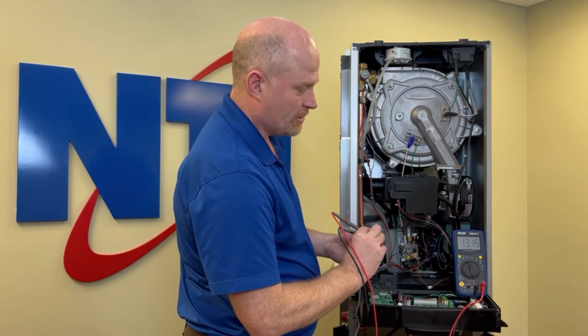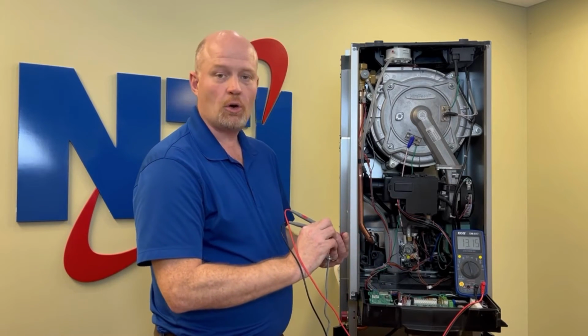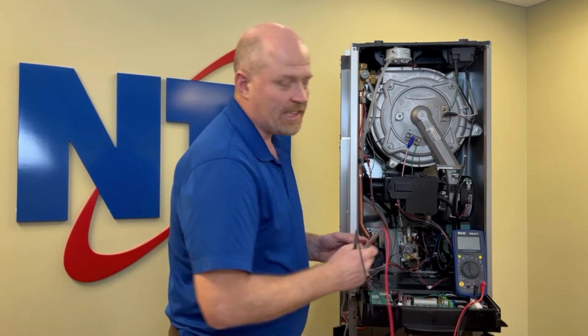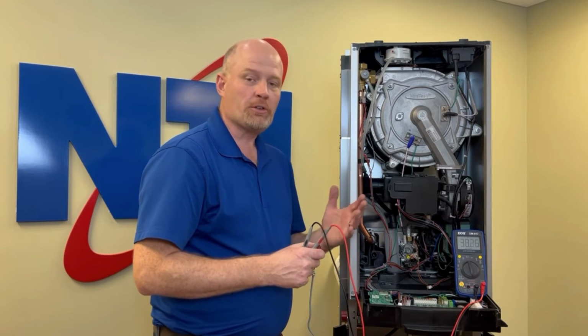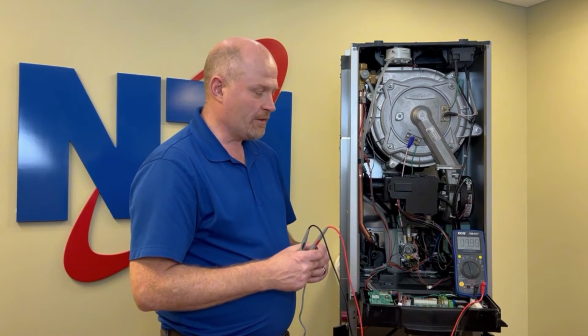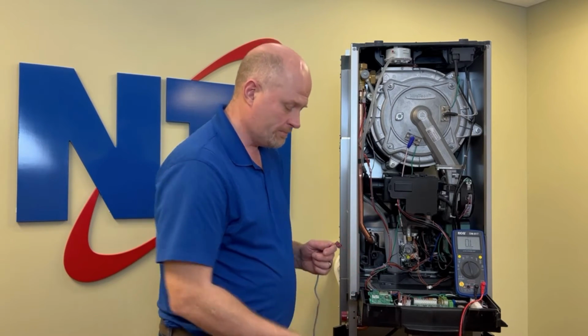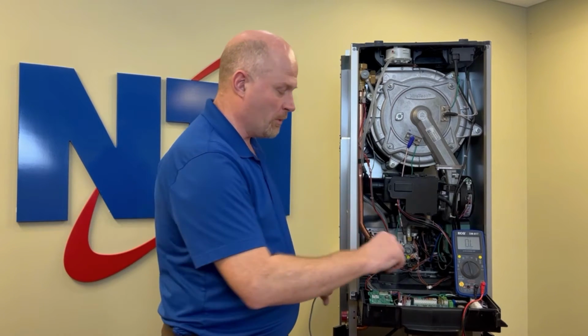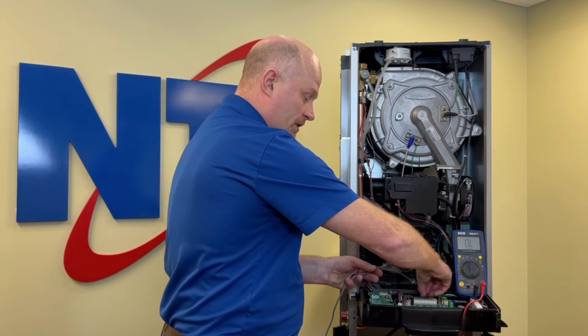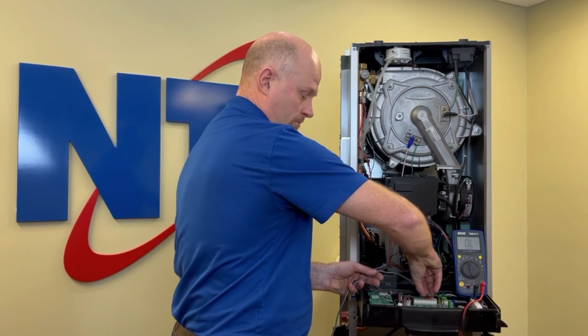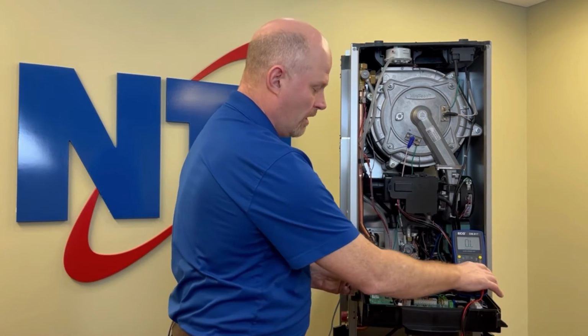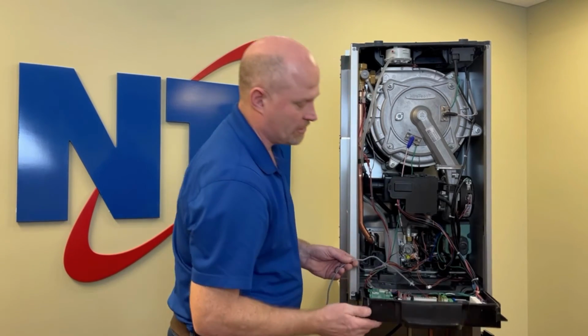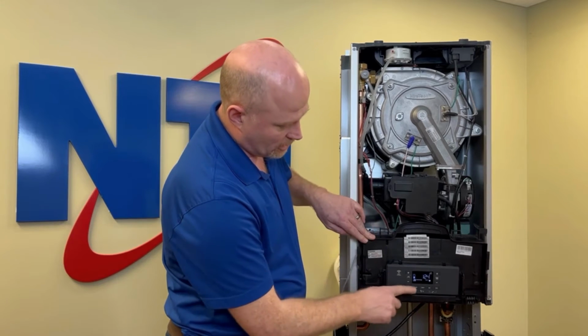So in this case, the resistance reading is 13,000 ohms. That would indicate that the sensor is providing a temperature somewhere in the region of 65 or 70 degrees Fahrenheit, and the sensor is working properly. At that point, we would want to make sure that it is connected securely to the circuit board. Once it is securely attached, the boiler will automatically clear the error if the problem is gone.